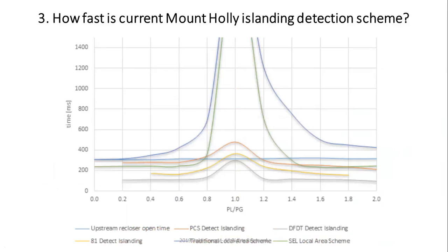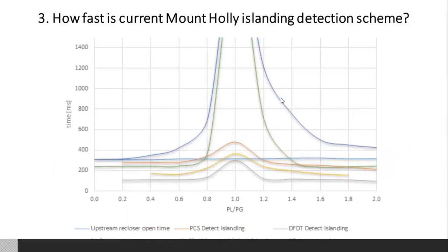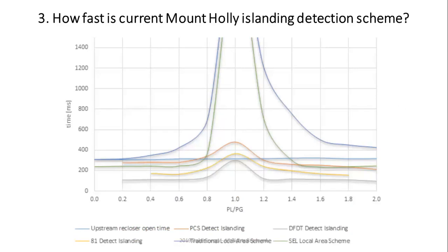The yellow line underneath is essentially the line that shows what would happen if we had 81 settings, right? The majority of the time on our system, it is the 81 setting that detects the islanding. And then last but not least, the bottom one that you can see, the fastest one, is called df over dt, which is the rate of change of frequency, which is much faster than 81, right? And I can just tell you, we did this test numerous times for different PL over PG ratios. You can see they go from 0.0 to 2.0. And with the scheme that we have implemented, that I showed you, you can actually detect this islanding with all 3 of these, right?